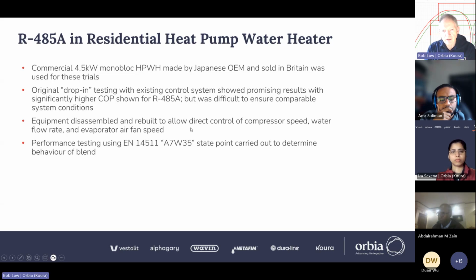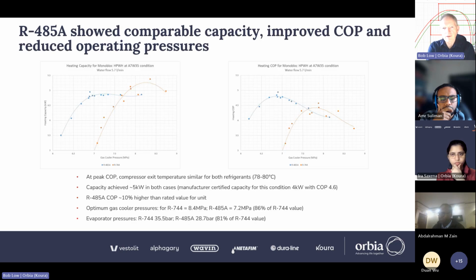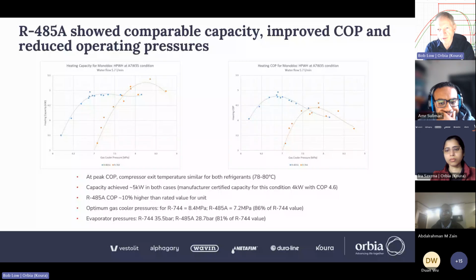So the following graphs are just a couple of points we did to match the standard for heat pump water heater performance testing. I think this point is A7W35, so that's air at 7 Celsius, water return from the house heat system at 35C and going back out again at 43C. And what we saw here in the two graphs are peak capacity as a function of gas cooler pressure, and then heating COP as a function of gas cooler pressure, the blend being in blue and CO2 being in orange here. And you can see here that we achieved about 4.8 kilowatts with the blend and just over 5 kilowatts with CO2. The rated capacity is 4.4 kilowatts for the unit, COP 4.6, and we matched that with both refrigerants pretty much. In this unit, we had a 10% COP gain at this point.